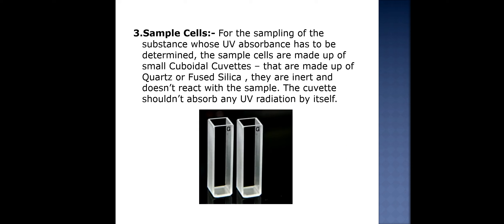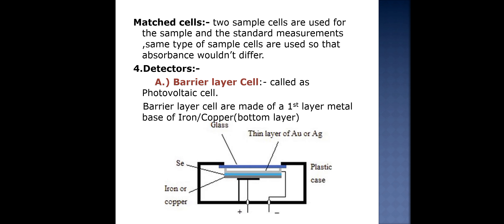The third instrument is the sample cell, used for sampling the substance whose UV absorbance has to be determined. Sample cells are small cuboidal cuvettes made of quartz or fused silica. They should be inert, must not react with the sample, and should not absorb any UV radiation themselves. Matched cells are used in double beam spectrophotometers where standard and test samples are studied, so that absorbance does not differ between the standard and the test.